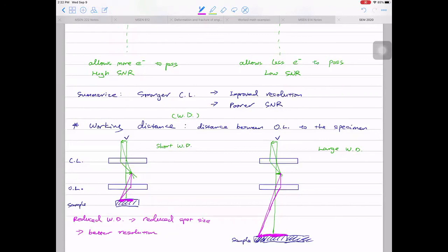If you use a very small working distance, you have to be very careful not to crash into the microscope. For example, someone was doing SEM on nanoparticles 5 to 10 nanometers in size, bringing the specimen to about one millimeter working distance from the pole piece — so close that if the sample has height variation, it could smash into the instrument. But the resolution achieved is simply amazing.